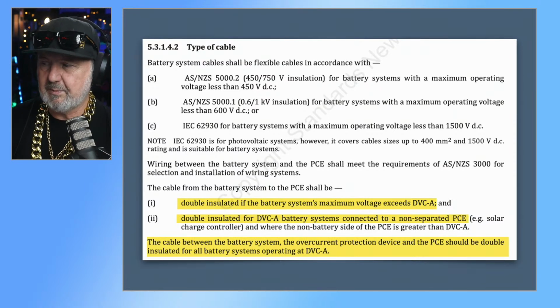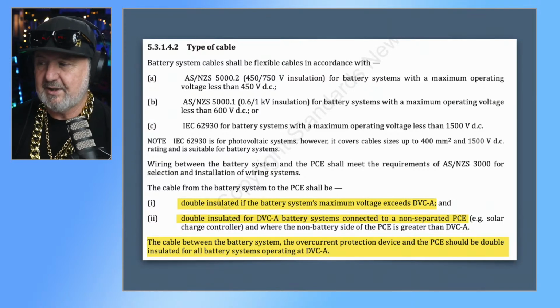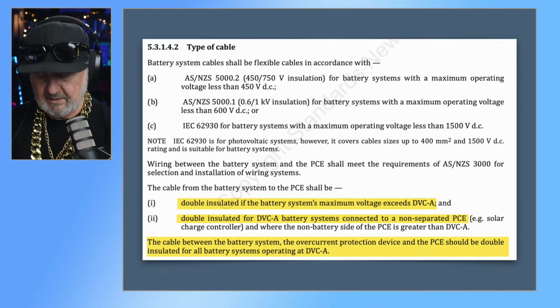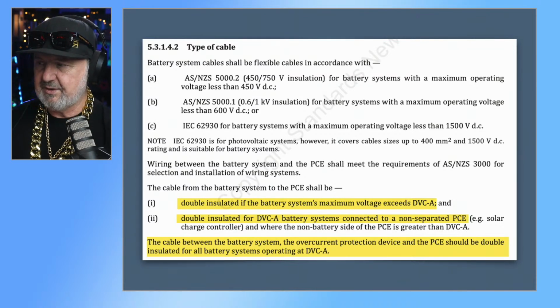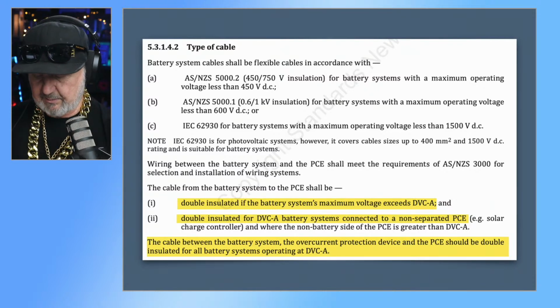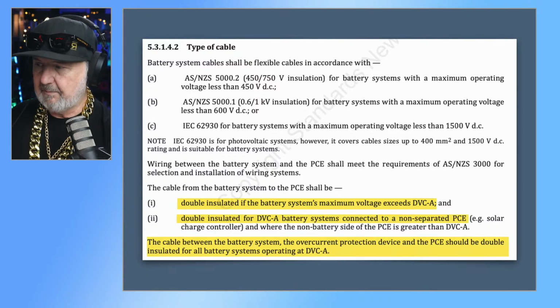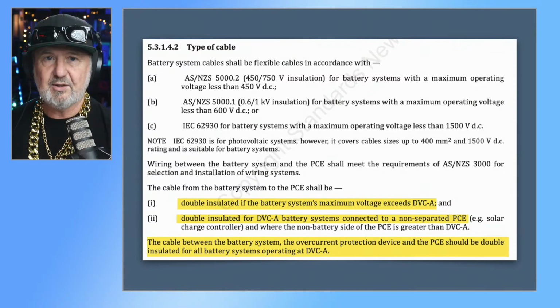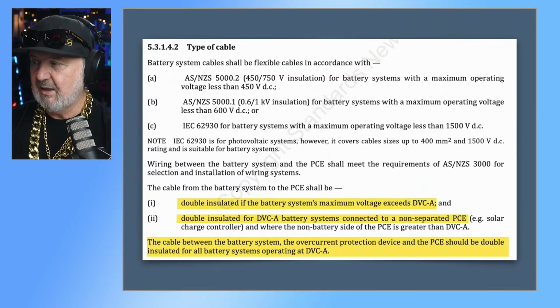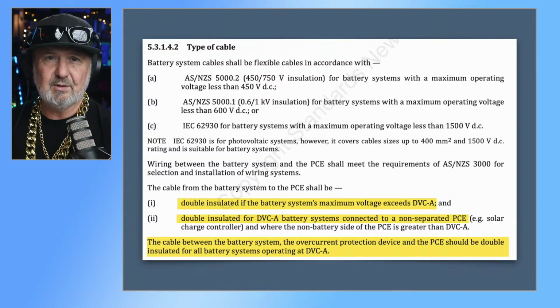So the cable from the battery system to the PCE shall be double insulated if the battery system's maximum voltage exceeds DVC-A. All right, so if you've got a battery over 60 volts, it must have double insulated cables. But down the bottom there it says, it's double insulated for DVC-A battery systems connected to non-separated PCE. Now, when I said non-separated, that means non-galvanically isolated, which is pretty much the case for just about all charge controllers. There's only very few that have galvanic isolation.